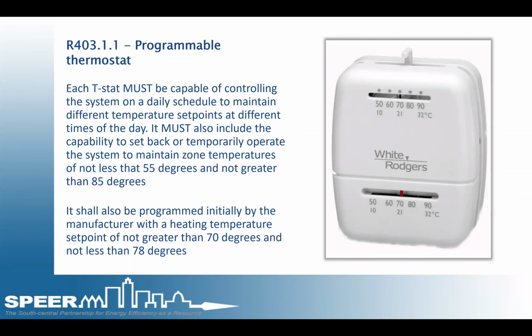If it's just set with the basics, anything after 7 or 8 o'clock at night it goes up or down depending on the season. And then it comes back on at, let's say, 6 o'clock when the workers, contractors or trades start to occupy the home. So before the homeowner moves in, all stats should be set to not more than 70 for heating and not lower than 78 for cooling. But the stat you see on the right is one that's no longer allowed by code because it cannot be programmed.